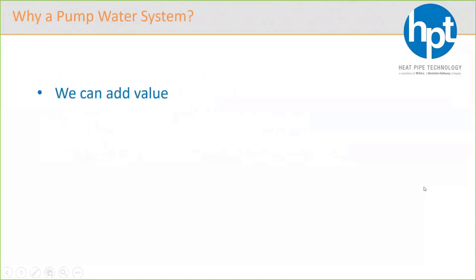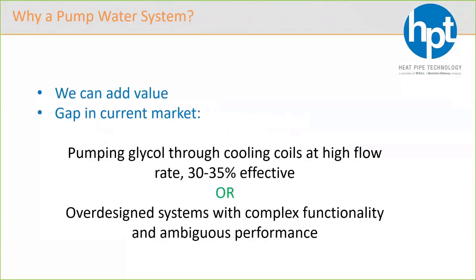Well, first of all, we really want to focus on air-to-air energy recovery where we can add value. And we have experience in air-to-air energy recovery, as I say, but also sensible recovery. So glycol was something that we showed interest in, and we think there's a gap in the current market. Why do we think there's a gap? Well, what we see is 2 types of solution in the market today.